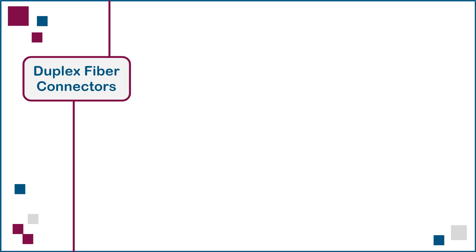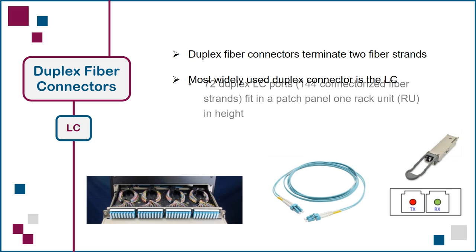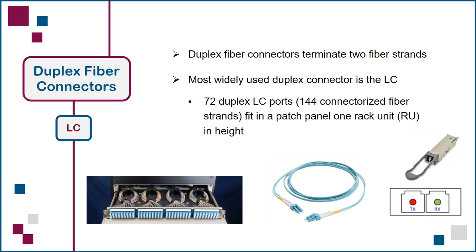Next, we'll summarize the two fiber duplex and multi fiber parallel connector options for a designer to consider when planning an optical fiber cabling system. Duplex fiber connectors terminate two fiber strands, and currently the most widely used duplex connector is the LC, with a density of 72 duplex LC ports, or 144 connectorized fiber strands, capable of fitting a patch panel one rack unit, or RU, in height. However, the continuous growth in network performance requires more fibers in the same amount of space, on both patch panels and optical transceivers, which means we need connectors with greater density than the LC.